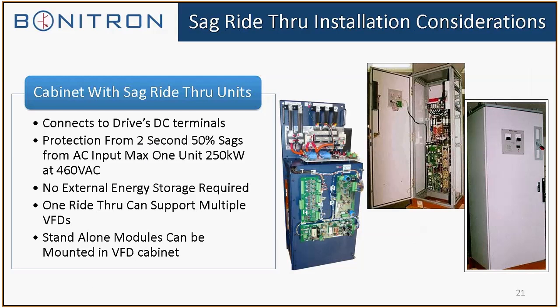Now, some installation considerations, but for SAGs, you have a single unit. It can go in the drive cabinet. As I said, I always recommend a DD4 display because it's a fantastic tool for being able to troubleshoot the ride-through and know what the initial indications are. Sometimes it's a simple problem that can be fixed in the field. Sometimes it's not. So the DD4 display will tell you pretty much what parameters are messed up, and it will allow you to monitor fault codes too, up to 30. We usually don't use that screen, of course, because Bonitrons don't fail, right?